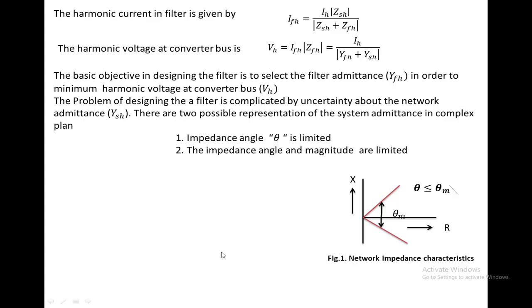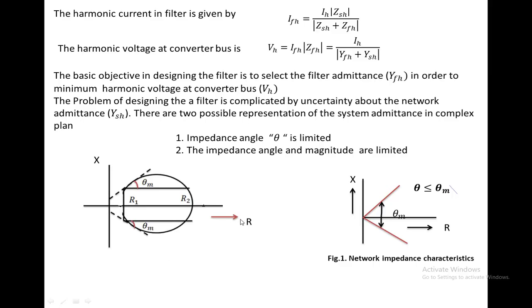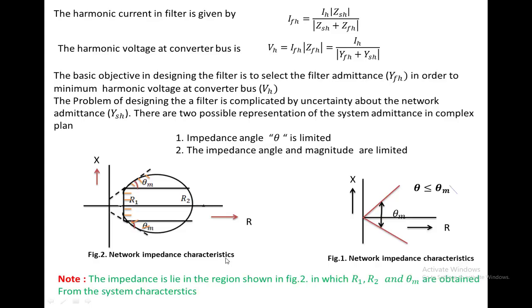The second method limits both the impedance angle and the magnitude. In this method we limit both the impedance angle as well as the magnitude of the system. The first method has fewer assumptions whereas the second method has higher assumptions for both impedance angle and magnitude. To apply the second method, we need a very clear idea about the system impedance or admittance — specifically the values of R1, R2, and theta_M that define the permissible region. The first method does not require as much knowledge of system characteristics.